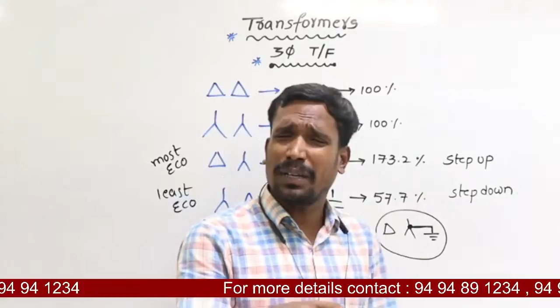For that reason, we use delta star with neutral grounding. But is a distribution transformer a step-up or step-down transformer? Distribution transformer is a step-down transformer. Actually, in step-down transformers, we should use star delta. But in star delta, there is no neutral point on the secondary. That's why we don't use this one - we want neutral grounding, so the secondary side must be a star connection.